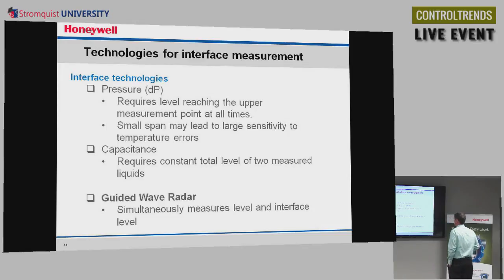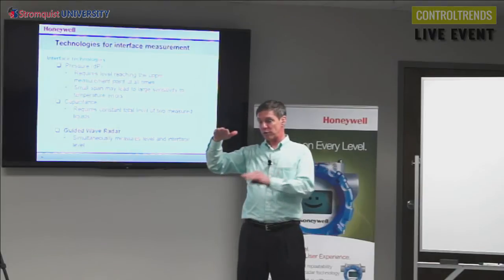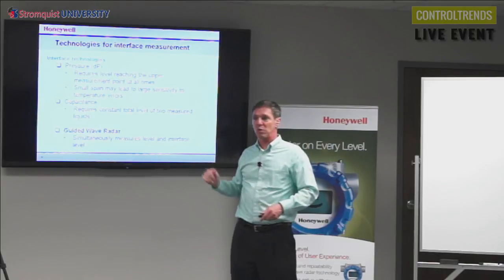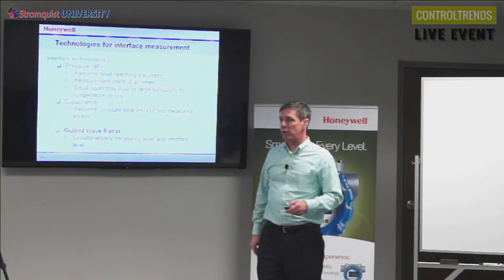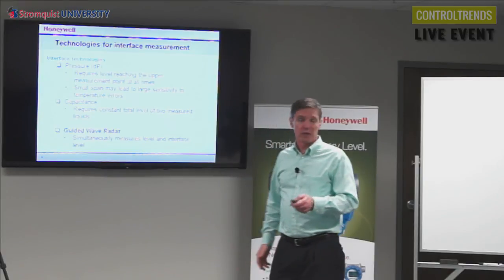Interface measurement. You can do interface measurement with differential pressure, but we said you have to keep that top surface level the same as the interface between the two changes. Okay? Same thing with capacitance. If you keep that top surface level constant, then you can monitor the change in interface between the two liquids. Guided wave, on the other hand, it doesn't matter. You can still raise and lower the surface while the interface between the two changes. So really guided wave is the best way to do interface measurement if that's something that the customer needs to do.